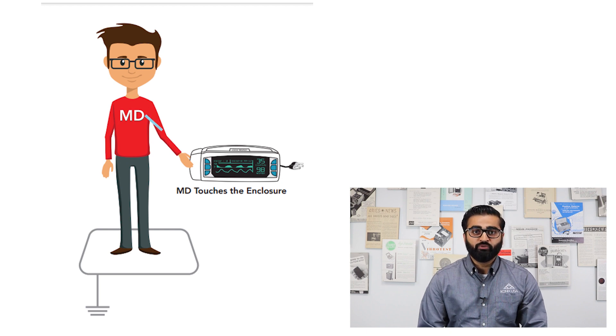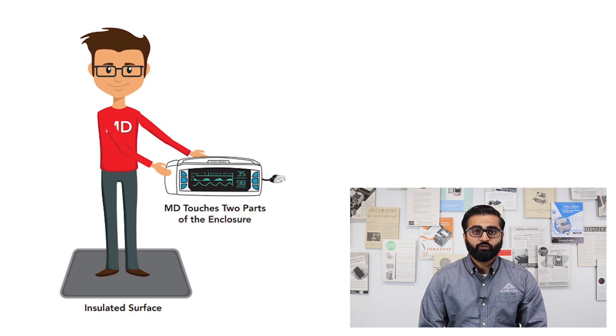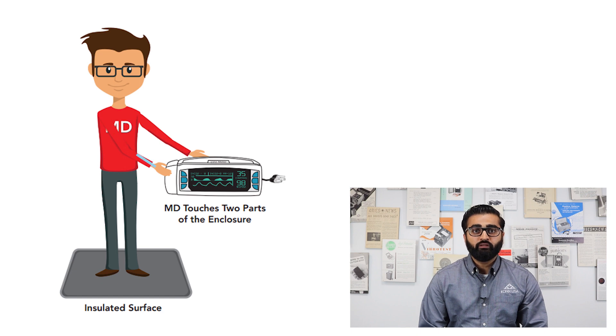The current is going to be generated at the enclosure point, travel through the measuring device to earth. Another way to look at a touch current point is between two enclosure points. In this case, the MD is placed between two enclosure points. Current is going to be generated at one enclosure point and returns back from another enclosure point.